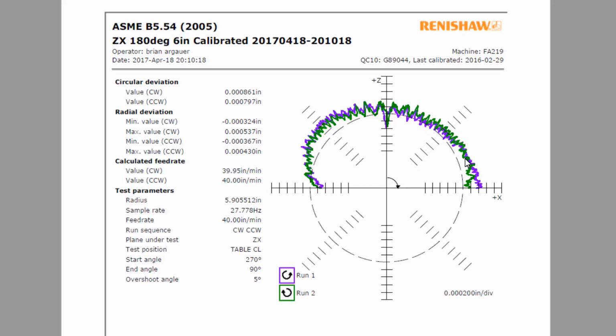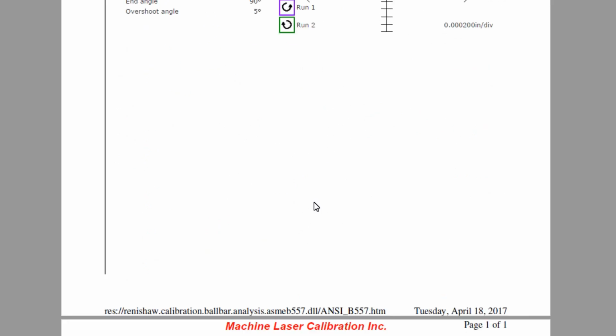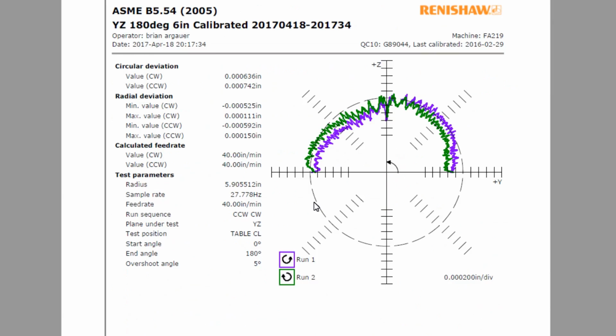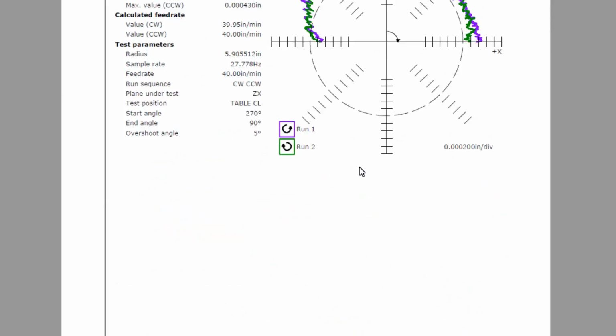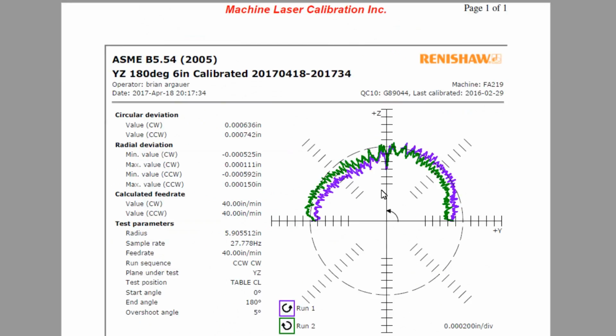This is what's called servo drive balance. So while the gain of the drive isn't bad, it's not running at the exact same rate in extend versus retract. We could probably get this a little bit better, but again, we're well under 1,000, so not too big of a deal. And here is YZ - it has a very similar plot. That's how you can tell, comparing XZ to YZ, that the Z servo axis drive could probably use a little bit of attention and adjustment.